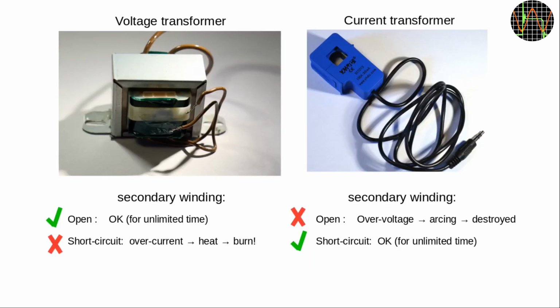It is very important that the current transformer is never used without a load connected to the secondary coil, because that can produce dangerously high voltages that can shock you and damage the transformer. In a sense, a current transformer is the complete opposite of a normal voltage transformer. A voltage transformer is quite happy when no load is connected to its secondary winding, but if you short it, the high current flow will cause it to overheat and eventually burn. On a current transformer, normal operation is when the secondary is shorted, or very nearly so, while it's in danger of destroying itself through arcing if no load is connected.